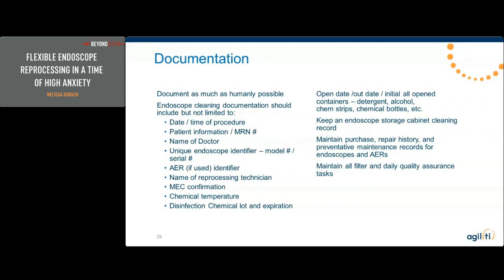And they borrowed from everywhere, and it took them a year to get back up to the full inventory and purchase in and get in their new items. But they also had to letter everyone over that 2.5 days that might have been exposed to prions that actually had a bronchoscope used on them. So this, like I said, this is a long time ago, but it always drives home, beyond just patient traceability, just how much trouble you can be in if you do not keep track of serial numbers faithfully and tie them to your loads.